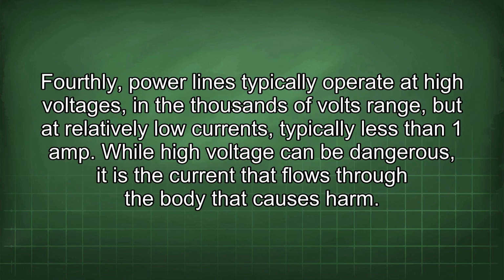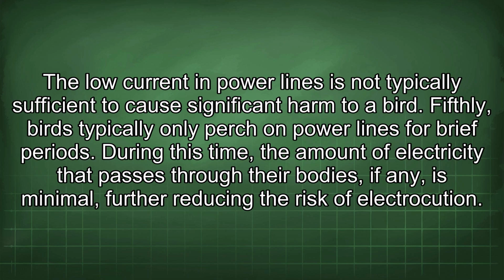Fourthly, power lines typically operate at high voltages, in the thousands of volts range, but at relatively low currents, typically less than 1 amp. While high voltage can be dangerous, it is the current that flows through the body that causes harm. The low current in power lines is not typically sufficient to cause significant harm to a bird.